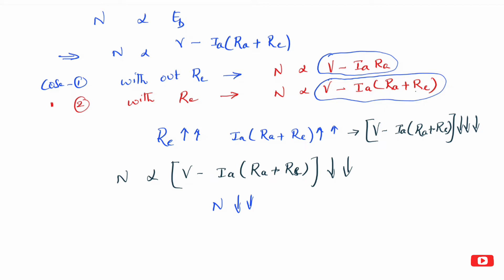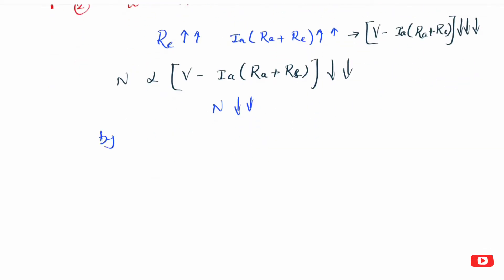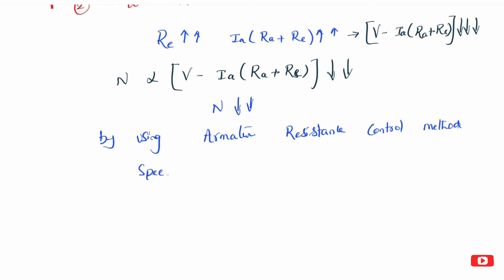So by using the armature resistance control method, we can control the speed. Speed can be varied below rated speed. In field control, speed can be varied above rated speed. But in armature resistance control method, speed decreases — so we can control speed only below the rated value.